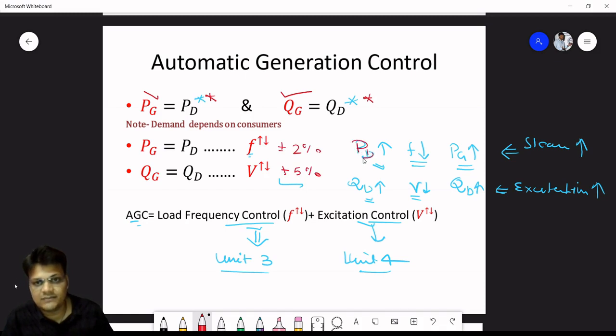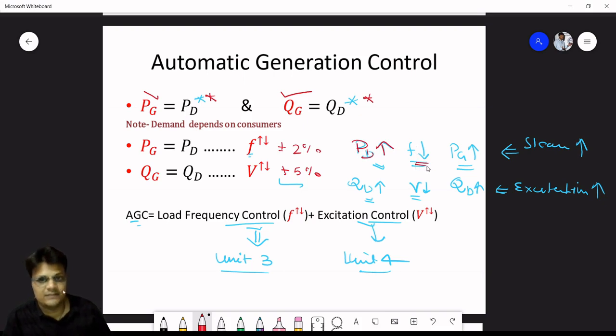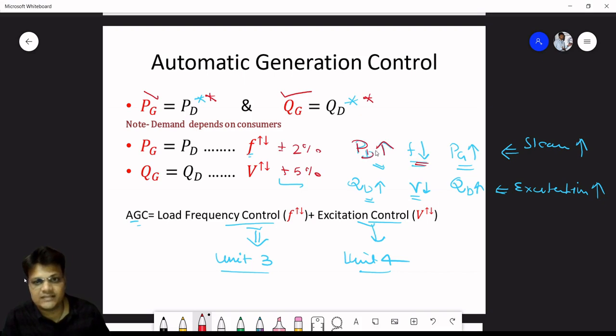When demand increases, frequency will decrease. So we have to increase generation to match the demand, so that frequency increases and the error gets zero. In a thermal power plant we increase steam input; in a hydropower plant we increase water flow.